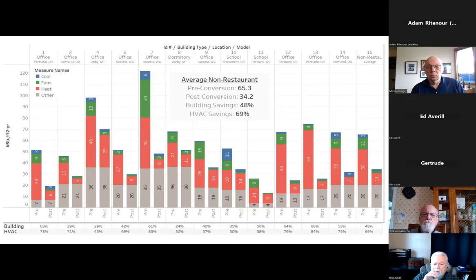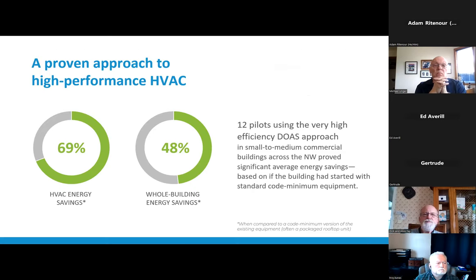But a key takeaway from this graph is you can see how it makes it difficult to just look at a building's utility bill and know how much HVAC conversion to a VHE DOAS will save. A lot of this has to do with fairly large differences in this other category, the gray category, which includes things like plug loads, lighting, or other machines in these buildings, and also differences in occupancy, ventilation needs, and schedules. There's a lot of variability between different commercial buildings. So each building and HVAC system is unique and presents unique challenges. With that being said, we see an average of 69% HVAC energy savings and 48% whole building energy savings. And that's from those 12 pilot projects. Again, we excluded those restaurants from this result.